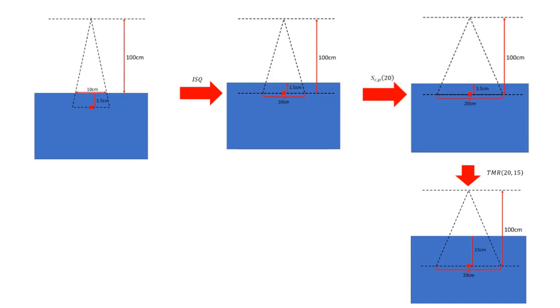This is just a nice illustration of how we can perturb the dose under our reference condition to the dose given the geometry that we're trying to calculate in. It is also a nice illustration of how we can take a Linac that was calibrated at SSD and actually use it to do an isocentric calculation. Also notice that our source to calculation point distance isn't changing here. We're always 100 centimeters away from the source. Since we're doing an isocentric calculation, we're always staying at that fixed distance.